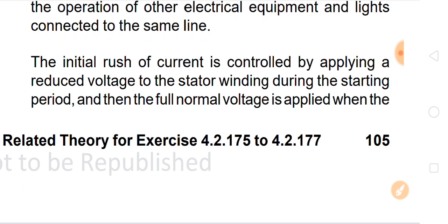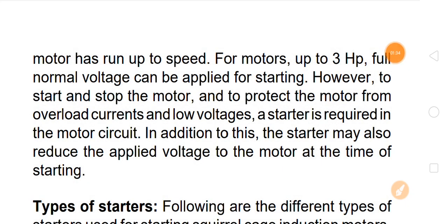The inrush of current is controlled by applying a reduced voltage to the stator windings during the starting period, and then the full normal voltage is applied when the motor has come up to speed. For example, up to 3 HP, full normal voltage can be applied for starting. However, to start and stop the motor and to protect the motor from overload current and low voltage, a starter is required in the motor circuit. In addition, the starter may also reduce the applied voltage to the motor at the time of starting.